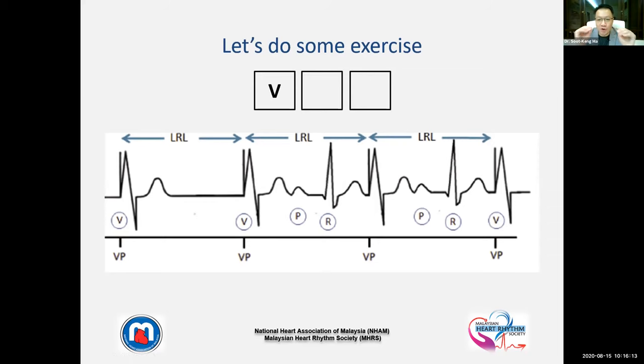Second alphabet means which chamber has been sensed. Now we can deduce that. Again, we are fortunate to have an intrinsic QRS complex here. Now, you guys look at the middle, it doesn't seem to affect the interval at all. So this QRS complex has not been sensed. And the P wave has not been sensed at the same time as well. So the second position is going to be O. If it's O, then the third alphabet must be O, because there's no sensing activity here. So this is one of the famous pacing modes that we use as asynchronous pacing for diagnostic purposes.